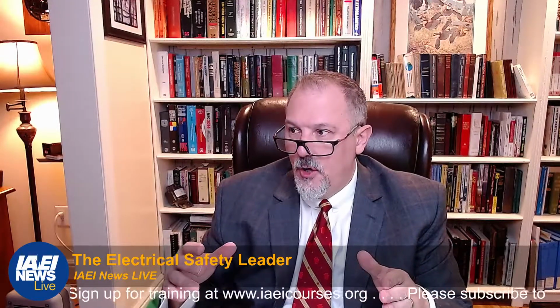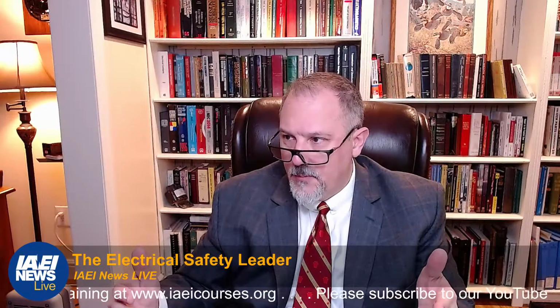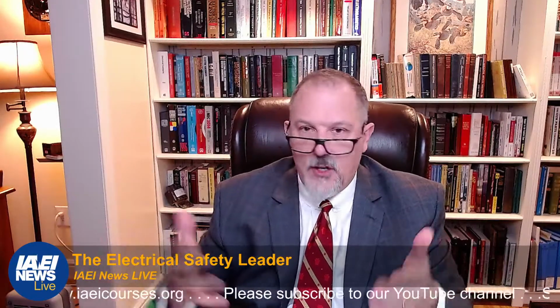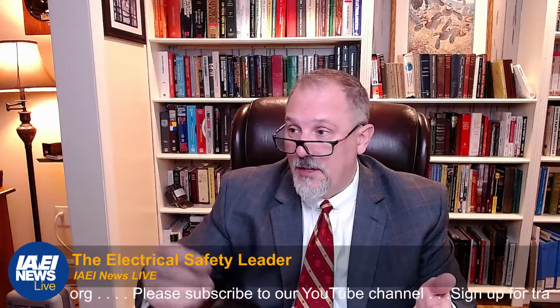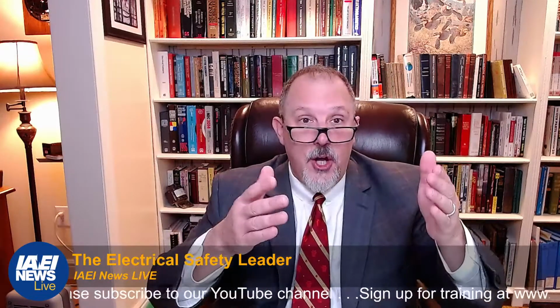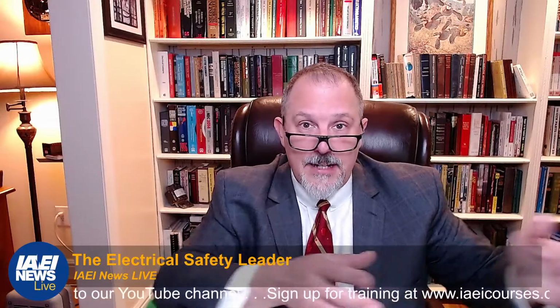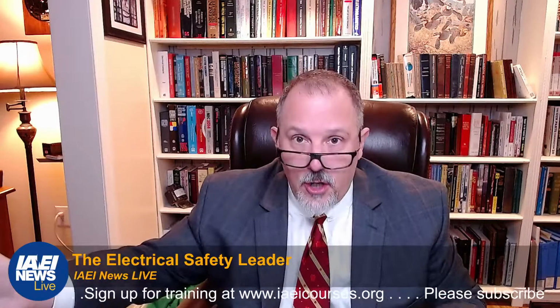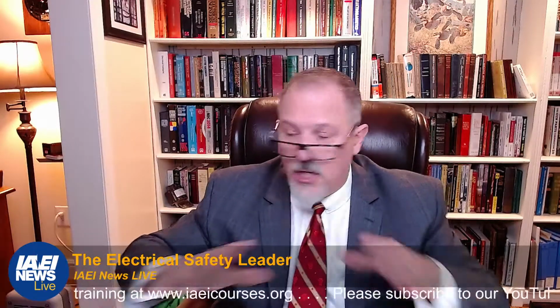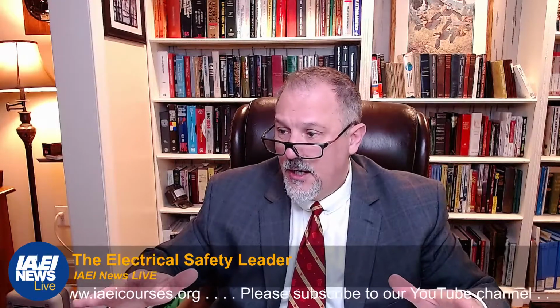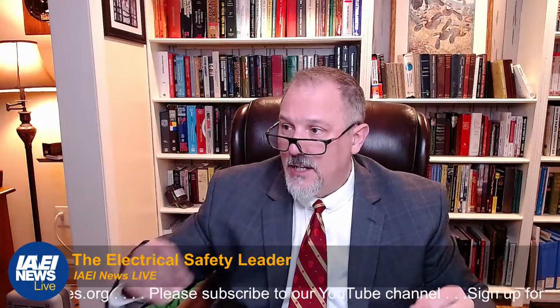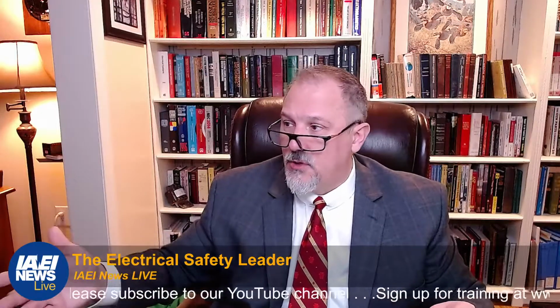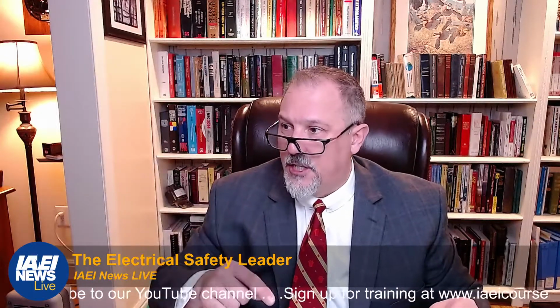And also, you have to identify when it's required. When the employee is within the limited approach boundary. When the employee interacts with equipment. When the equipment is properly installed, the equipment is properly maintained. When the rating of the equipment for available fault current is adequate. The equipment is used in accordance with instructions. The equipment doors are closed and secured. All equipment covers are in place. There's no evidence of impending failures. And they go through that list. So energized electrical conductors and circuit parts operating at voltages equal to or greater than 50 volts shall be put in an electrically safe work condition before you perform work. And they give you all of these conditions.